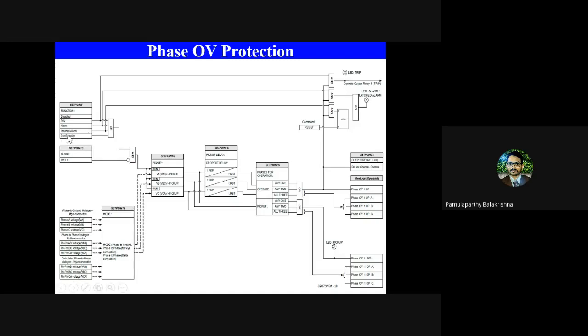Okay, another option is configurable. Configurable means any of the two actions, or you can define your own action. Like apart from trip and alarm, you want to communicate to an upstream device, or you want to inform the operator through a message in his app. So different things, if you want, you can configure it yourself as configurable. Basically this setting defines how this protection function has to behave in the field, meaning what action it has to take when it sees an overvoltage condition. Second thing, as I told, block defines whether to take any control action or not. Unless it is unblocked, it will not execute. Now we have defined what action it has to take and whether it is blocked or not.